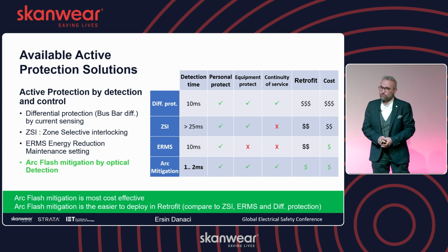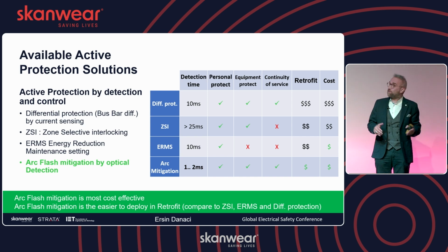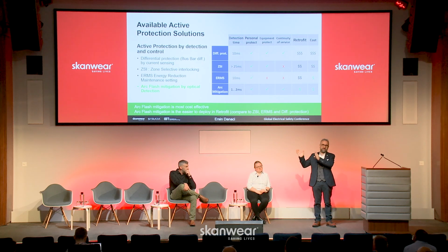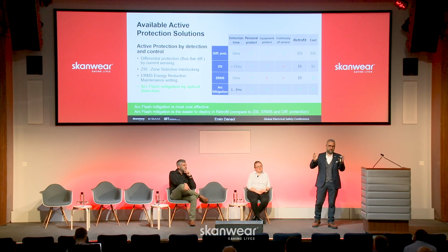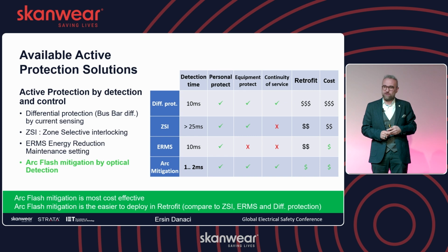I want to recap the arc flash mitigation approach. We started with the first risk assessment, then talked around the system study, arc study, and energy calculations. Then we talked about arc mitigations like PPE, passive protections, arc energy tunnels on switchgear. Now I'll talk more about active protections, with arc flash protection relays.